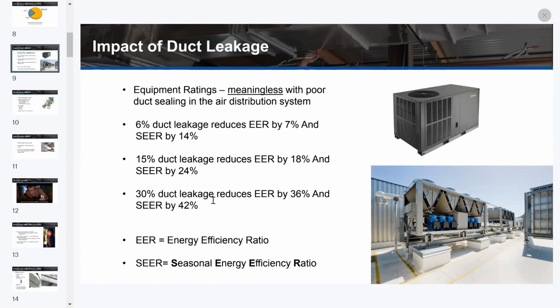So Lawrence Berkeley National Lab did some testing and came back and said that if you had 6% of duct leakage, it reduces your EER by 7% and your SEER by 14%. By the time you get up to 30% duct leakage, it reduces your EER by 36% and your SEER by 42%. And when you look at some of the data, typically, a residential home, back when LBL did this testing, was leaking on the range average of 25 to 30%. So when you have a really nice big SEER unit sitting outside of your house and you have ductwork that's not sealed, you have some system effect issues and all that, you're just really not getting the benefit of that equipment.